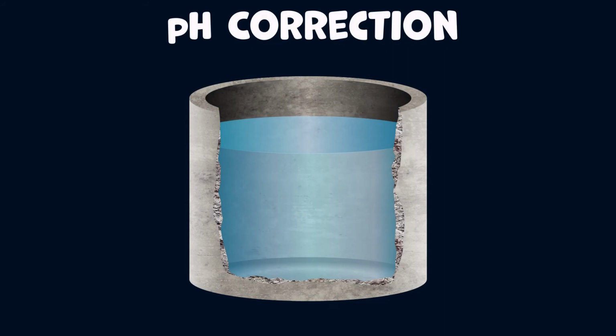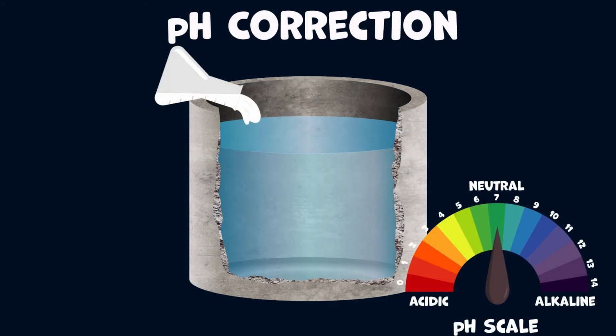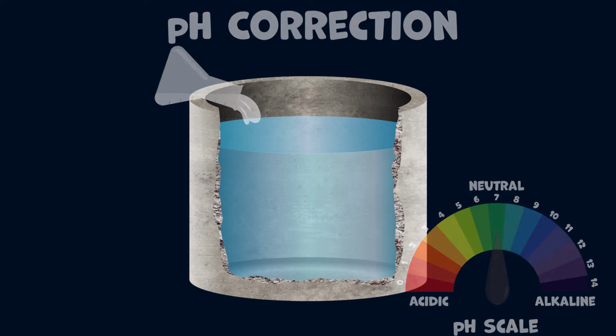A chemical called lime is added to the water at many of our plants. Through the treatment process, the pH is altered and the water becomes slightly acidic. If we sent the water to homes while it is an acid, it would gradually eat away at our pipework. Adding lime takes away the acidity or neutralises the water.